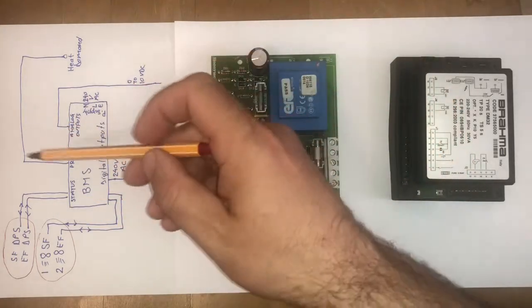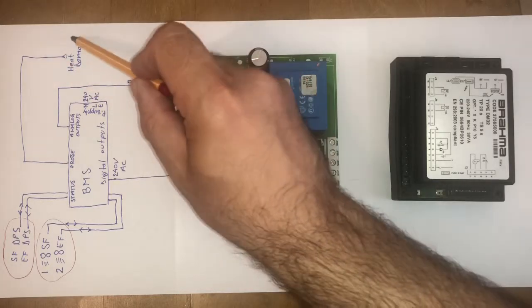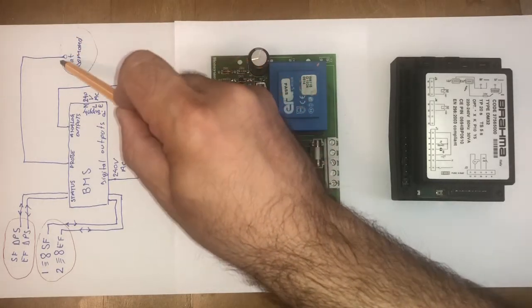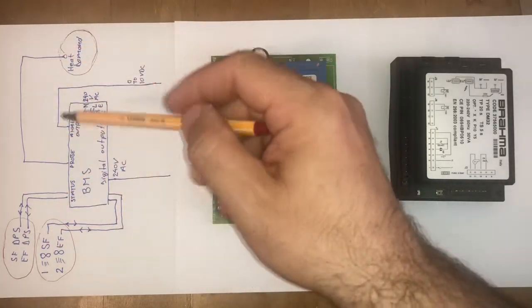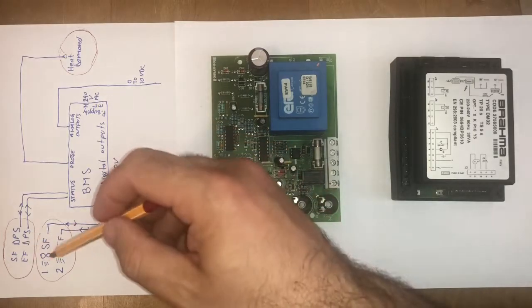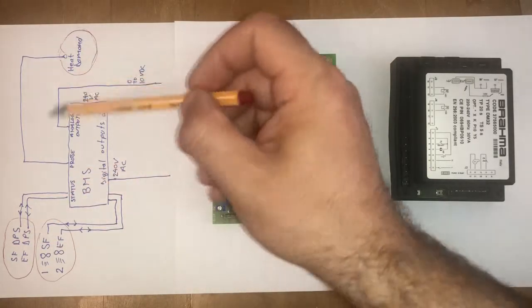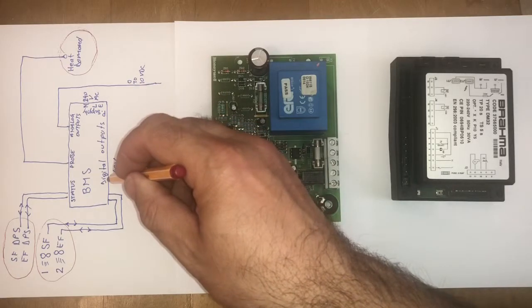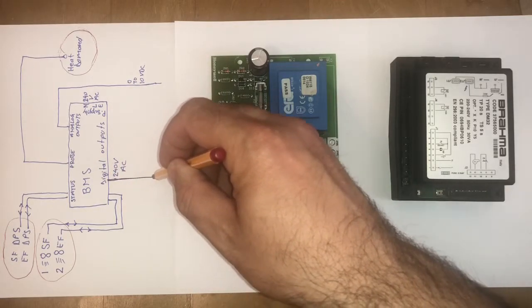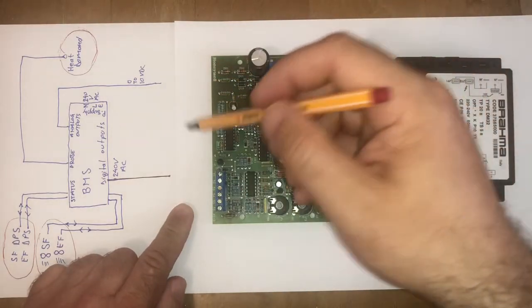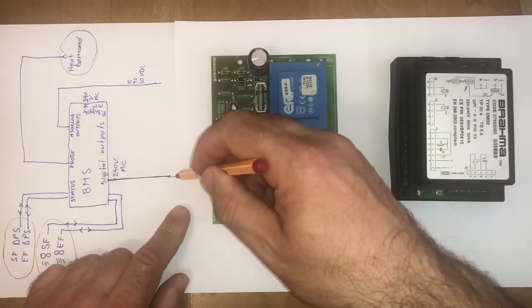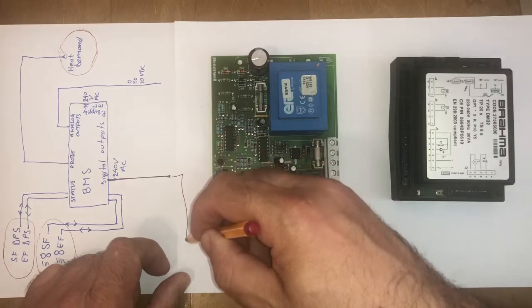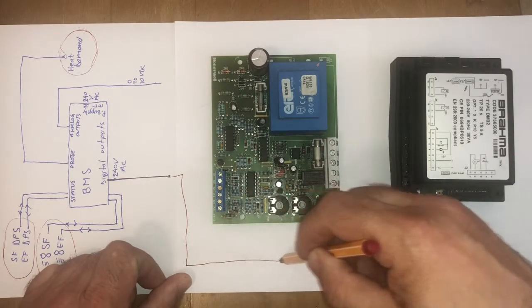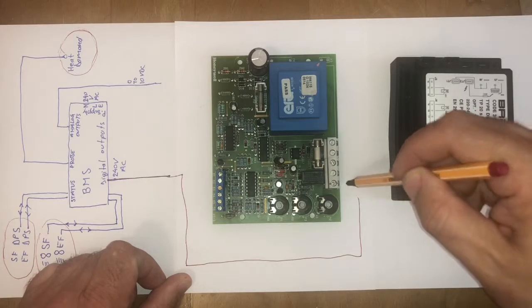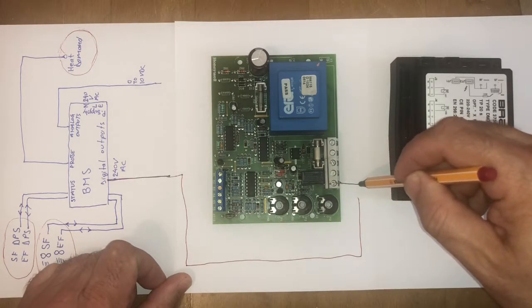In that case, the building management control already has a heat demand. As I put here, we have a heat demand. So if you have the heat demand, you obviously start the fans. So the fan runs, the DPS gives the healthy information, and obviously we have the heat demand. The building management control will enable and will put the system on standby mode. We'll send 240 volts to this free voltage relay.